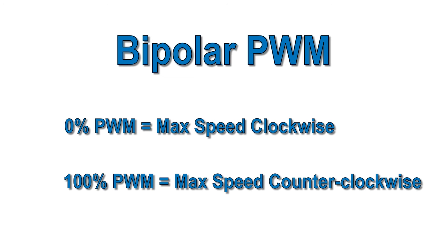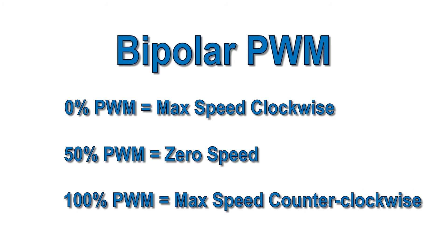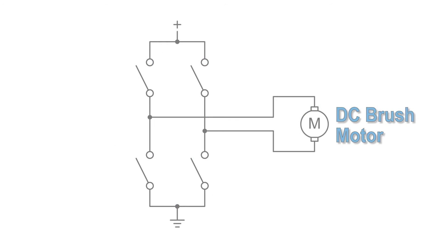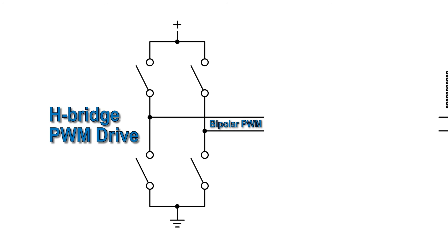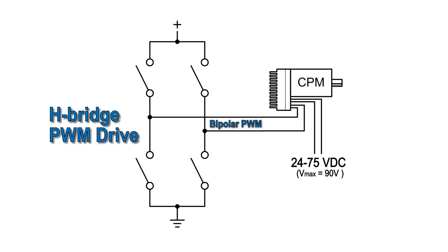Finally, ClearPath has a bipolar PWM mode, where zero PWM and 100% PWM correspond to max speed in opposite directions, and 50% means zero speed. This mode is perfect for those of you who want to replace brush motors powered by H-Bridge PWM drives without having to change any software. That's because H-Bridge drives naturally output bipolar PWM. You just hook the drive output to ClearPath's PWM input, and you're done.